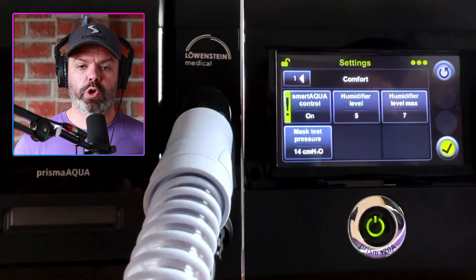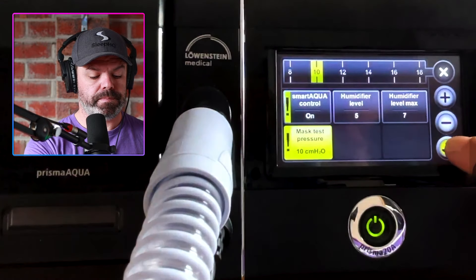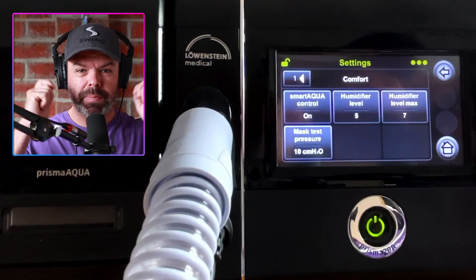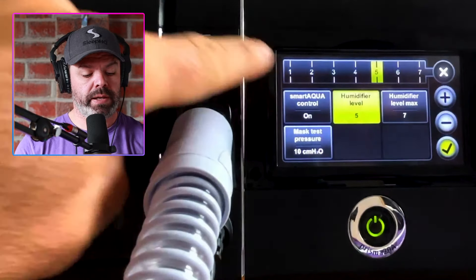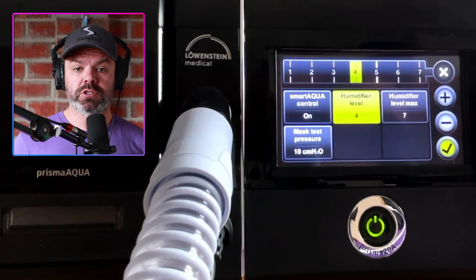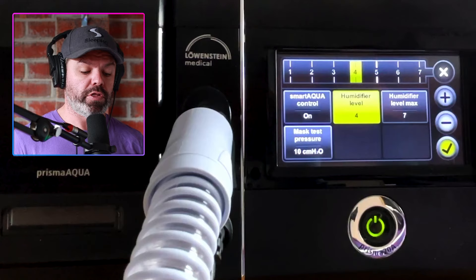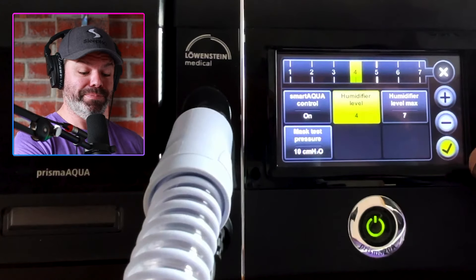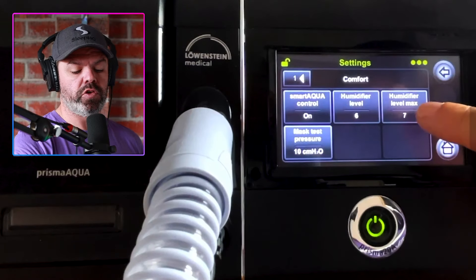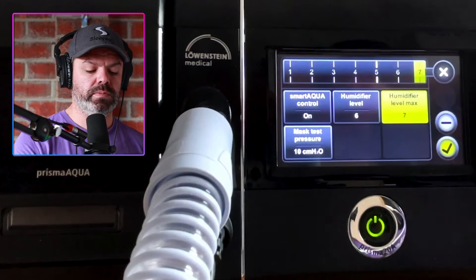Mask test pressure — you can run a pressure test at whatever level you choose, say 10 centimeters, and the machine will check your mask seal prior to sleep so you can make sure it's adjusted correctly. Humidifier level runs from one to seven: as you increase the level, the rod temperature increases to deliver more water vapor — great for dryness of the mouth, nose, and throat. The humidifier level max is a clinician control to limit how high you can go, but we want that set to seven.